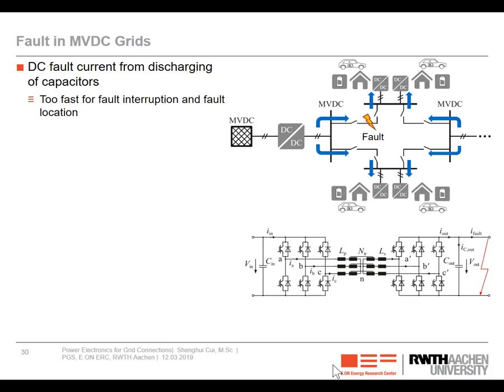So today we are also looking at the so-called breakerless medium voltage DC concept. We are asking ourselves if it's possible to operate a DC grid without circuit breakers at all, and manage the fault current in an active way. So here, in such a DC grid, if we say a short circuit fault occurs here, then we know that this capacitor will be immediately discharged, right? And the discharge of this capacitor only takes 1 or 2 microseconds. It's very, very fast. So basically, we can do nothing to control this time period.